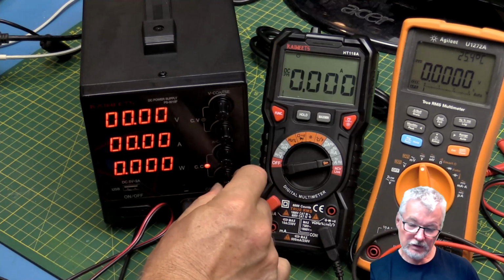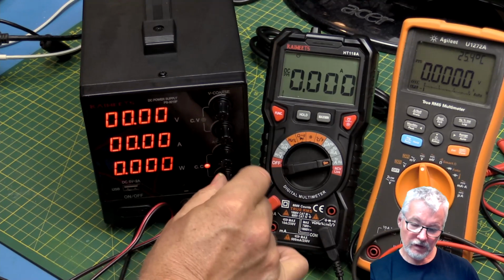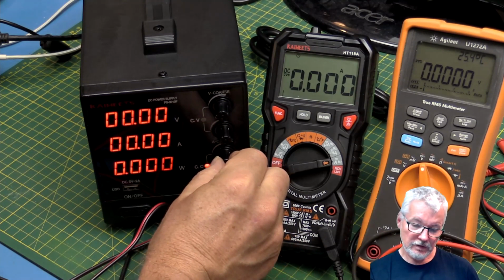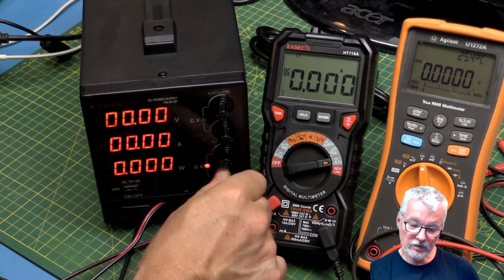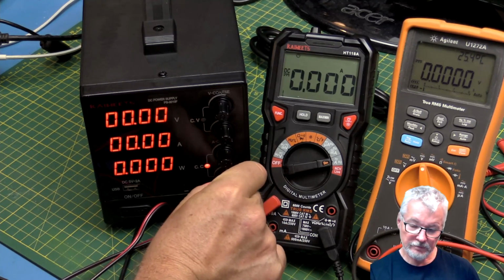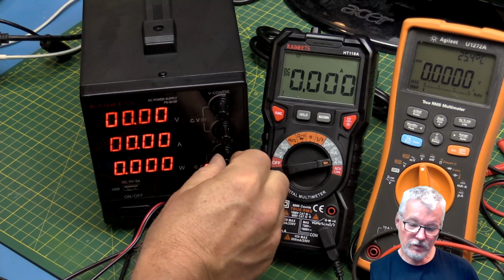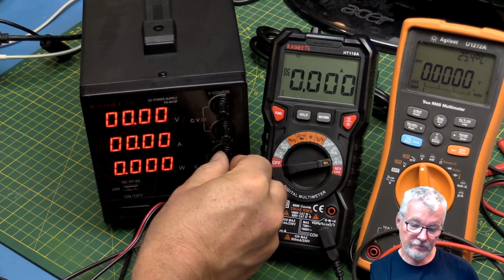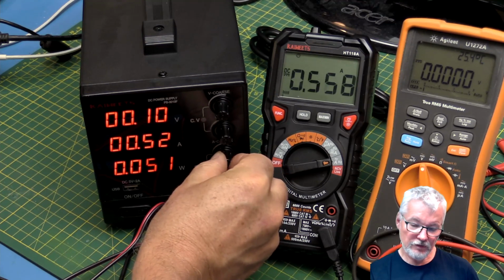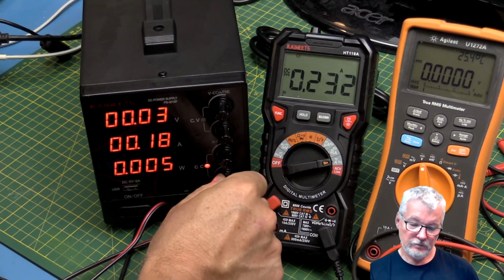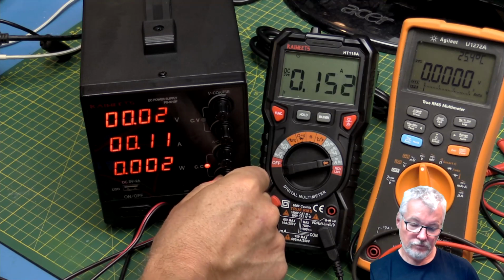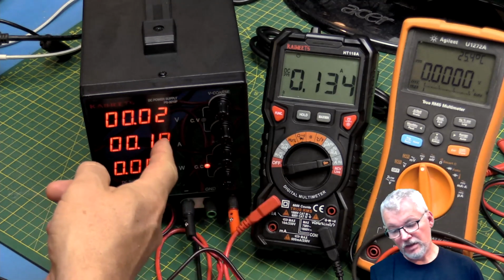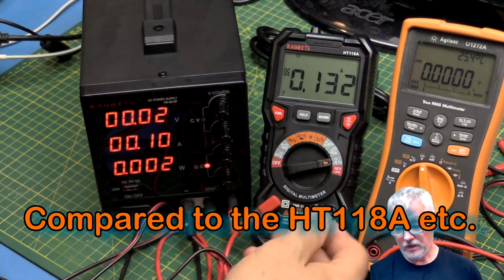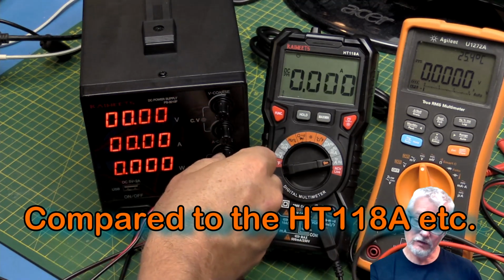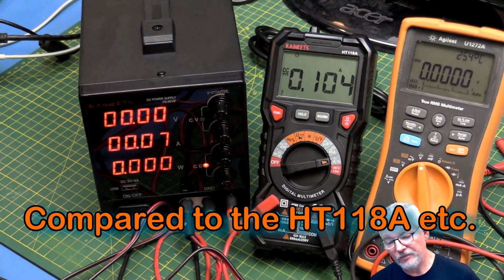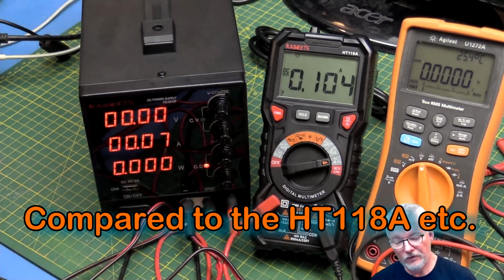It probably should have. That's a minor calibration detail. I won't give it any bad points for that, but the way to do this then would be to set this pot, the fine adjust, in the middle, roughly, and then tweak your current up. It's going to be very difficult to set. Yeah, but that's only 10 there, so it's 10 something. But as I said, it's reading a little off. Yeah, it's a little bit difficult to set that, but at the low end it's a fair bit off.